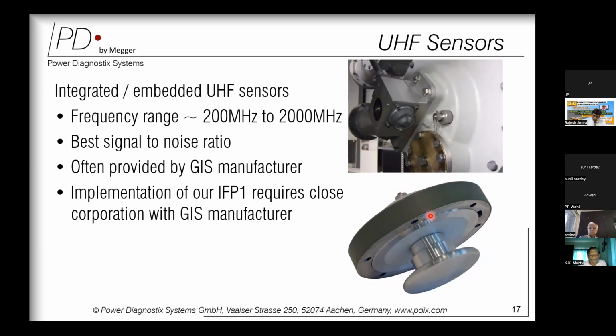Since the antenna is embedded inside the GIS, it provides the best signal to noise ratio. The only thing required is that you have to ask the manufacturer to provide this inbuilt UHF sensor. That is something you need to take care of whenever you are going to buy a new GIS. Quite often in 110, 220 or 400 kV GIS, the manufacturer will provide you these sensors. But if you have any lower rating GIS, then you have to ask the manufacturer to help you with this inbuilt UHF sensor, so that in future you can use it for partial discharge measurement.